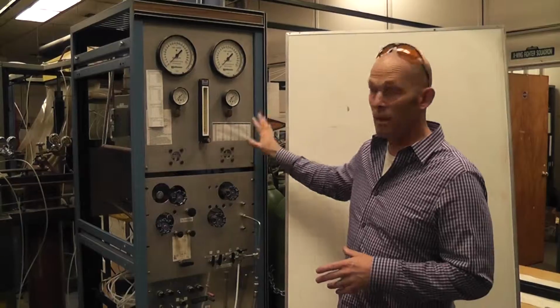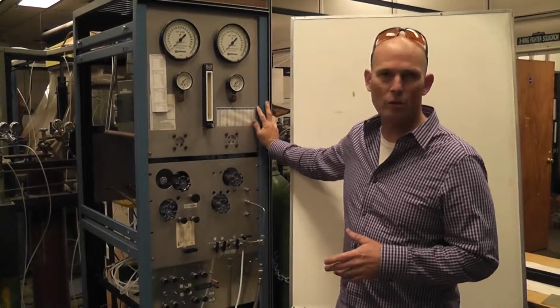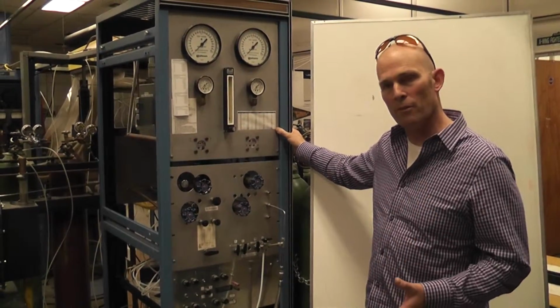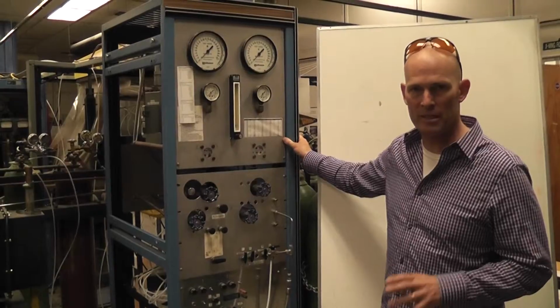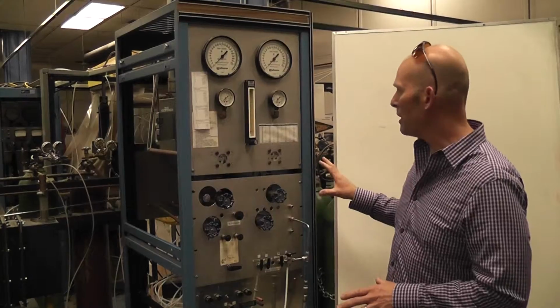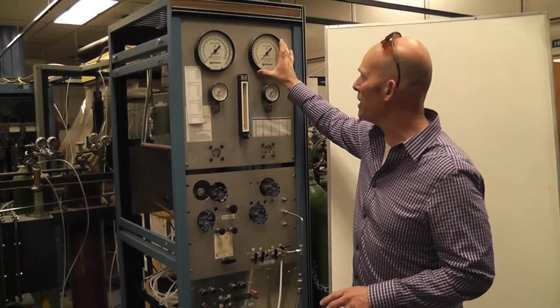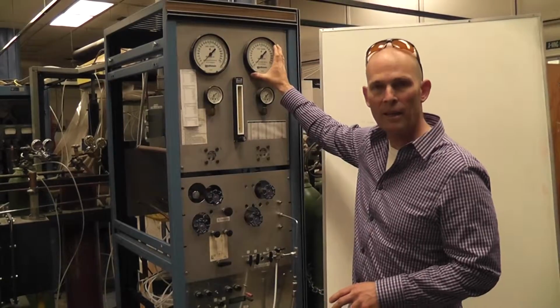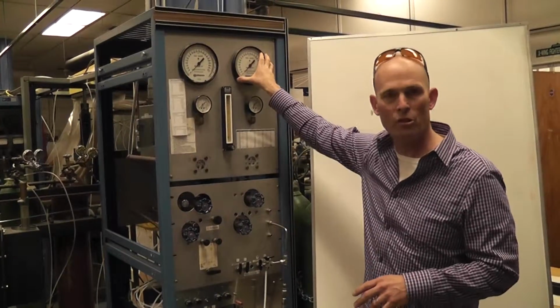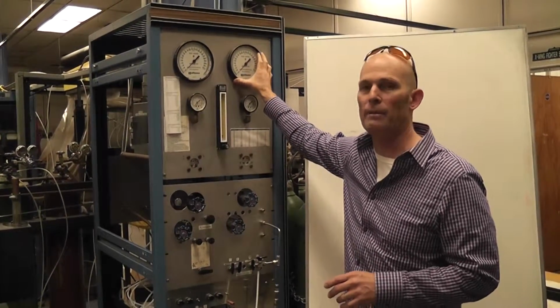Okay, I'll tell you a little bit about flow control devices for the measurement of gas flows here in the laboratory. I'm standing in front of a panel that has a lot of piping behind it. It's a fairly typical flow control panel, at least here at the university, for controlling the flow rates and mixing rates of various gases. So this particular panel can control probably as many as 3 different gases. These 2 gauges would each control the flow of one gas, and they do it through what's called an orifice plate. I'll come around to the back side of the panel and show you where that is, and we'll talk in class a bit about how it works.